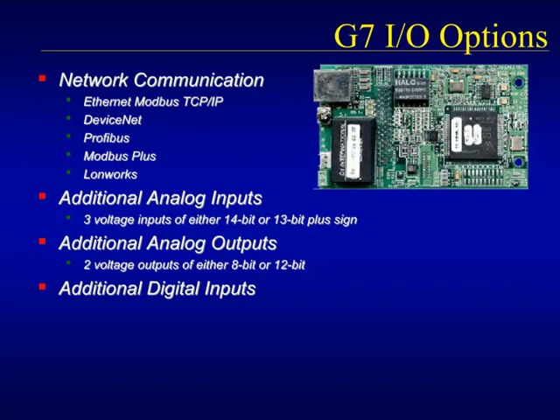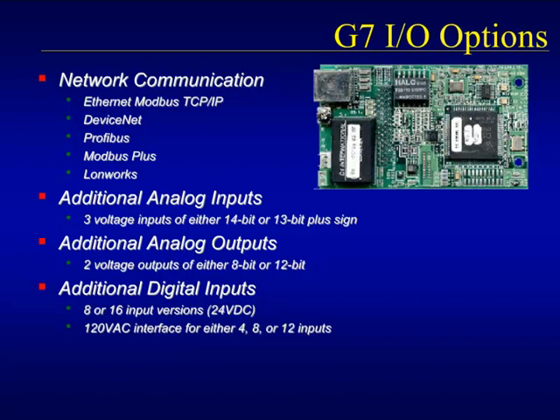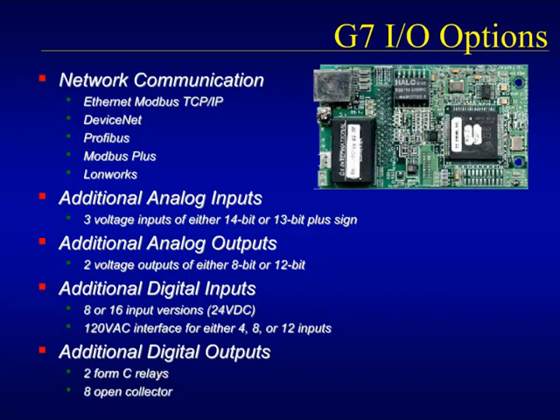The need for additional digital inputs is met by option cards that provide either 24 volt or 120 volts AC inputs to add to the drive's standard digital inputs. An optional digital output card will bring the drive's output count up to 6 relay outputs and 10 open collector outputs.